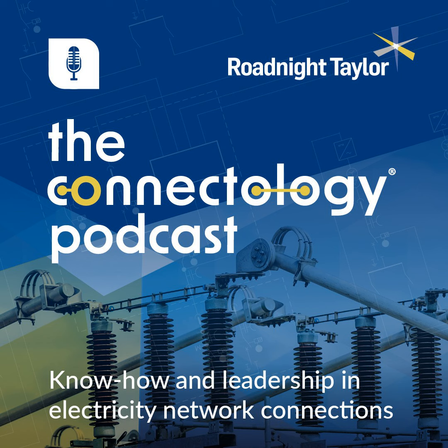There always has been an underlying principle that the transmission system has to be economically designed. So it is not worth the cost to GB consumers to make sure that every generator has firm access from day one. So connect and manage, which people have heard about for so long, effectively mandates connecting people as quickly as possible, and then designing the most economically efficient transmission system to be able to deal with that. So that might still involve there being some constraints. So generator constraints, curtailment actions on the transmission system have been around for a really long time.